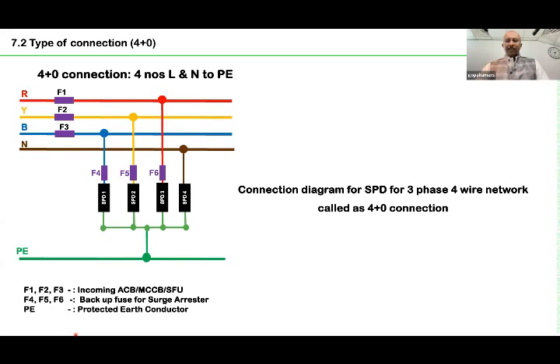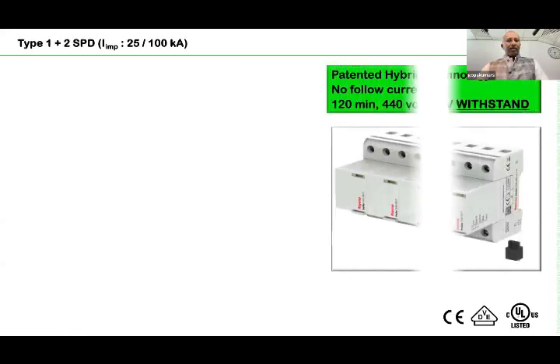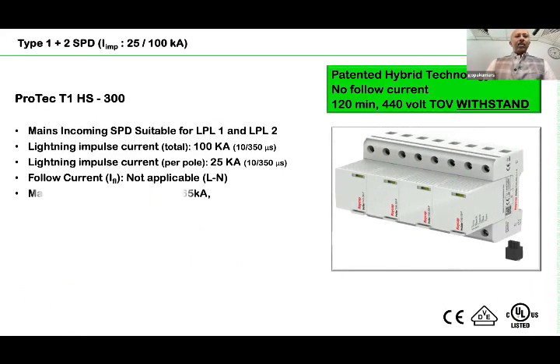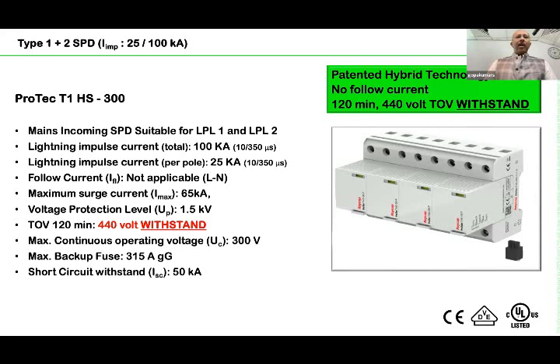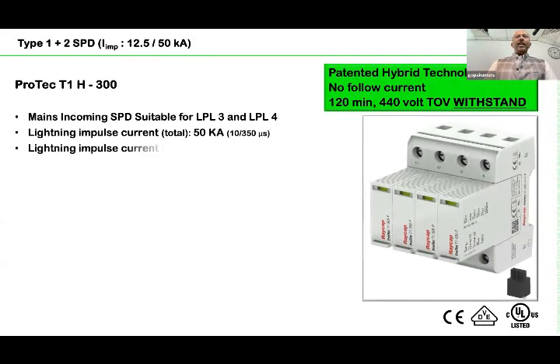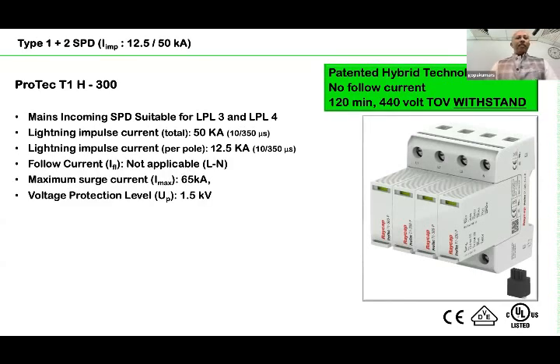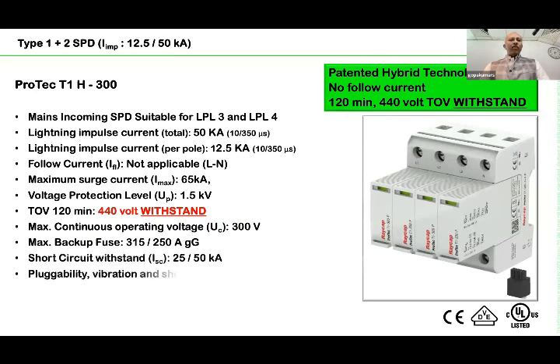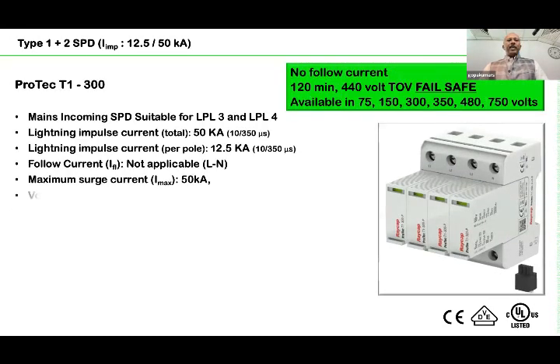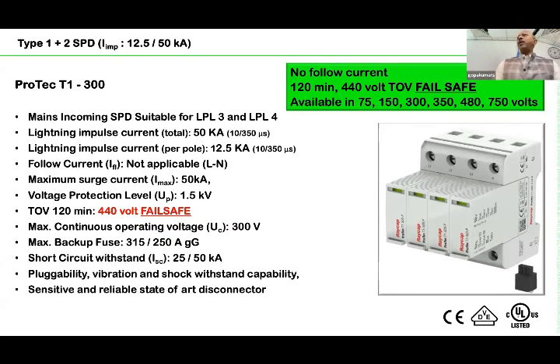Now, one moment. I will just touch upon the SPDs, some of the models, for example. This is called a type 1 SPD, 100 kiloampere. I'm sure if I give the data sheet, you can read it very well. No need to explain too much. Similarly, another type 1 SPD where the current is only 50 kiloampere, the voltage protection level is 1.5 kV and so on. Another type of SPD. So basically, if you look at our catalog or our website, you will be able to find hundreds of types of SPDs. So selecting the suitable one, that is the engineer's job.